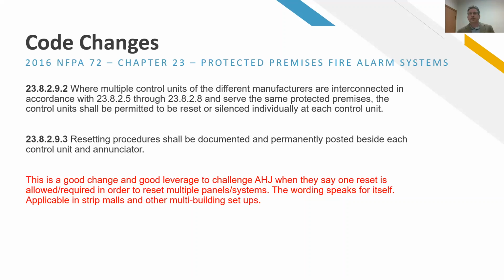So here's a good section, good leverage for the owner in that situation where you have a building with multiple fire alarm panels. For whatever reason it ended up that way -- maybe it used to be multiple tenants and you bought the whole building, now you have the whole thing and it's multiple systems. The authority having jurisdiction comes in and says, hey, we can only have one point of reset for this entire building, and you've got five fire panels. Well, this is leverage that actually says it's okay to be able to reset those. Yes, it's a pain to reset them individually and in the right sequence so you don't have a cyclical alarm that trips the other panels again.